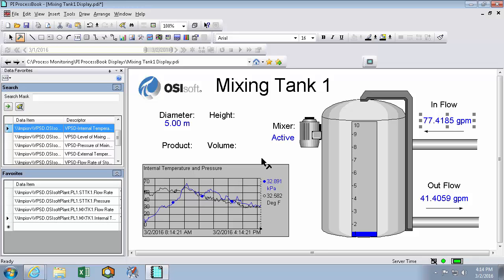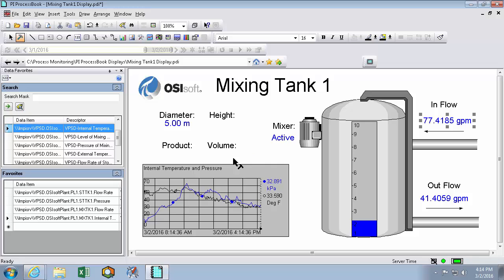But you'll notice that we don't have any PI points for height, product and volume. This is because these element attributes are defined only in our PI AF database. This combined with the often unfriendly nature of the PI point naming conventions really highlights the value you get out of a well-constructed AF database.